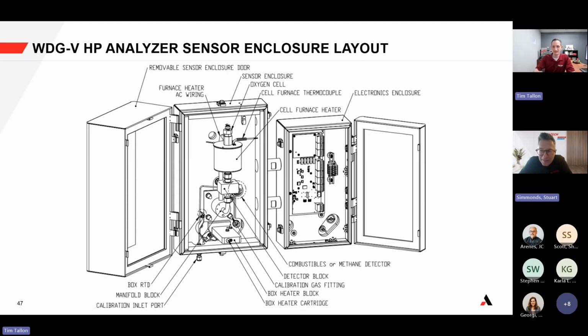Yeah, it's awesome. I think that's important. We have a lot of applications where these are outside, up in the air, and the catwalk is 3 foot wide. Taking the analyzer off is awkward, requires more than one person usually, and there's not a lot of room. Even pulling a 3 or 4 foot probe across those is somewhat awkward, but at least it's manageable, and usually a one-person job. That helps with limited resources on the sites these days. So I think it's a very clever design. That deals with the practical nature of what we have to deal with, for sure.